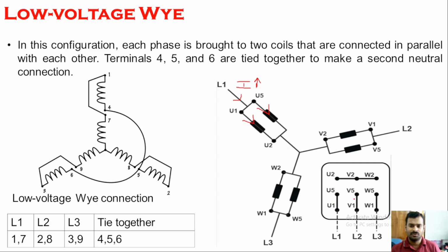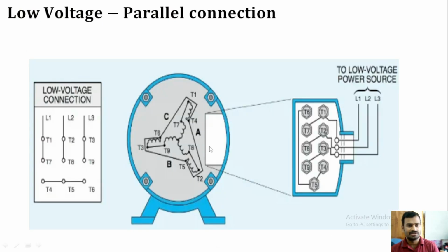When we get this kind of motor, on the nameplate or the connection terminal, you can see U2, V2, W2 shorted, or terminals 4, 5, 6. These 3 terminals will be shorted. 1 and 7 are connected, and connected to L1. 2 and 8 are connected to L2. 3 and 9 are connected to L3. The remaining terminals 6, 5 and 4 are interconnected. When we connect like this, this leads to low voltage star connection. And when you want to connect it for high voltage, we will see in the next slide.